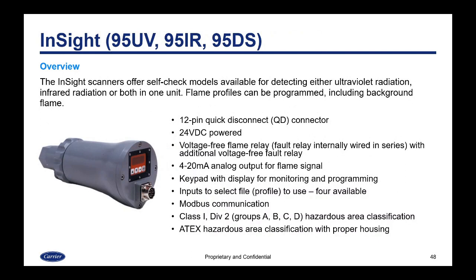The InSight scanners offer self-check models available for detecting ultraviolet radiation, infrared, or both in the same unit. This one has a 12-pin quick disconnect, is 24 volt powered, and has a flame relay, fault relay, and 4 to 20 milliamp analog output. It also has a keypad with display for monitoring and programming, inputs to select a fuel profile — with four available profiles — and adds Modbus communication. By default it is Class 1 Div 2 rated and can be ATEX hazardous area classified with a proper housing.